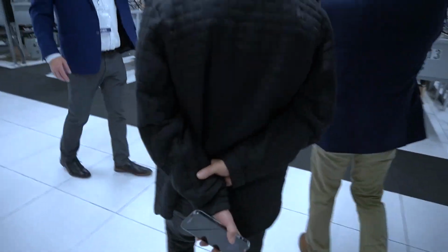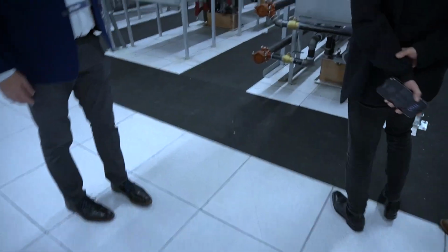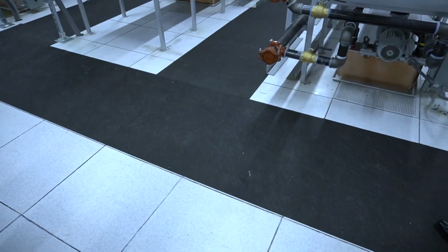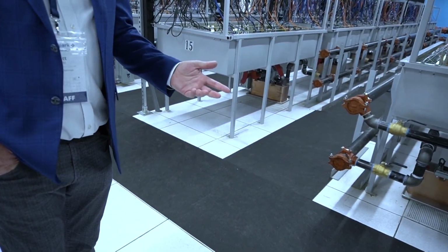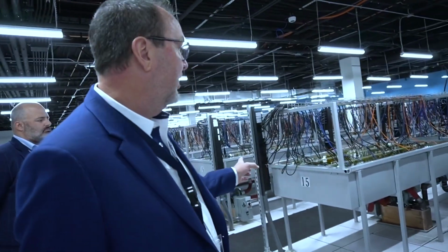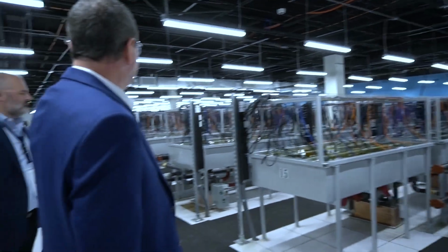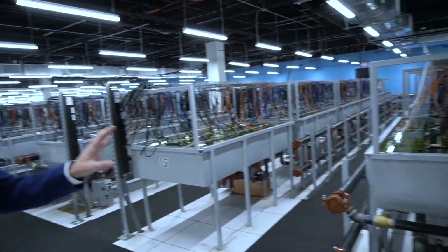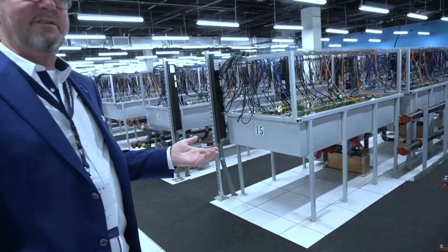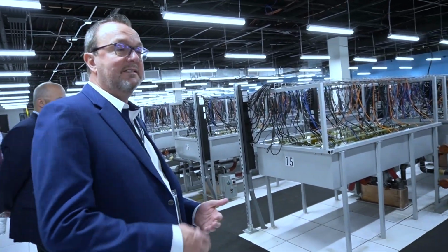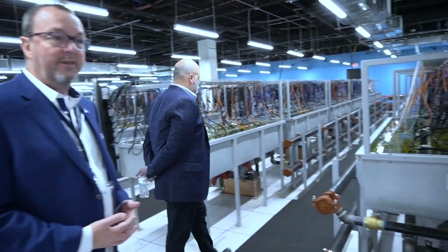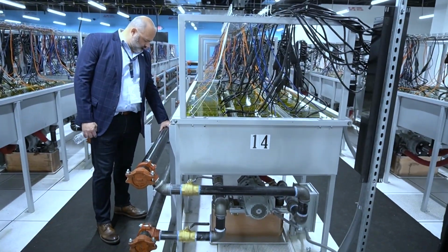So where the section we just left was cubicles and office space, this facility is 87,000 square feet, we have 7 acres. Now this is phase 2. The dry coolers, the operation is exactly the same as you saw in phase 1. The difference is this deployment is 12 megawatts, 50% more than what you saw before. As you walk down this deployment, you'll notice that towards the end, the oil in the tanks changes. That's a test we're doing with Shell. They've designed a new synthetic mineral oil intended to be more efficient at removing heat.